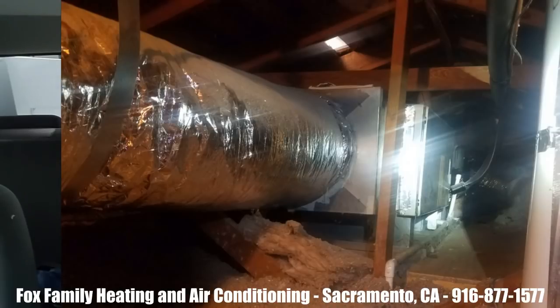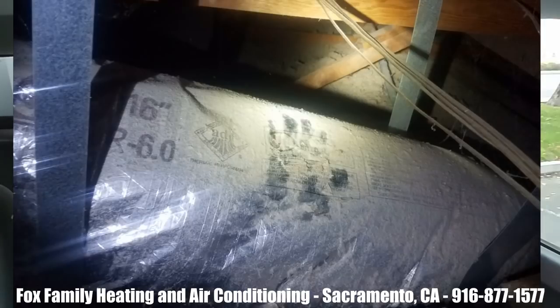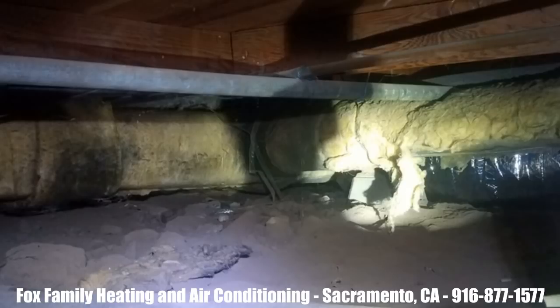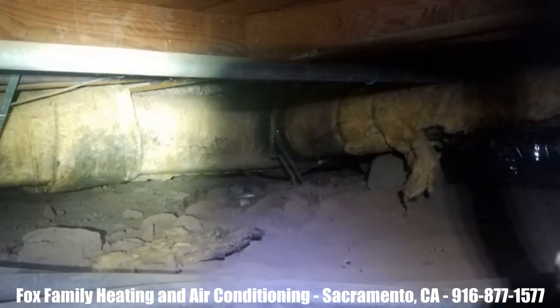He's got decent return — 2 16s coming in for return air, giving close to 2,000 CFMs. But he's only got one 16 coming off the supply. That 16 goes from the attic split system down through a closet, down through a chase, into a big elongated rectangular chase, and then the ducts branch off from there.